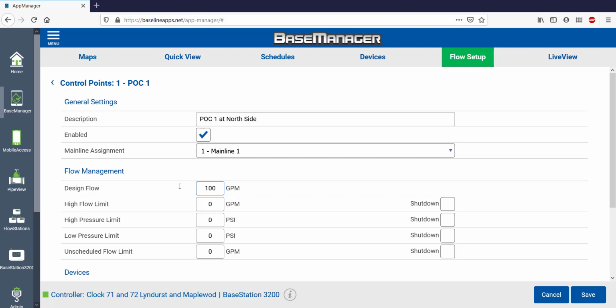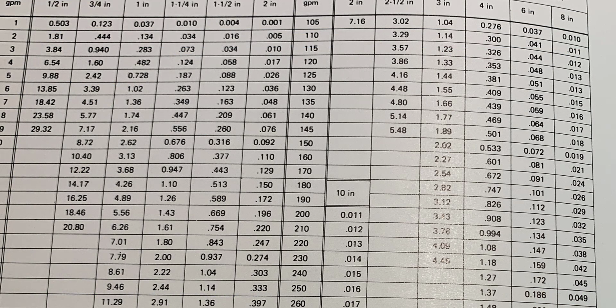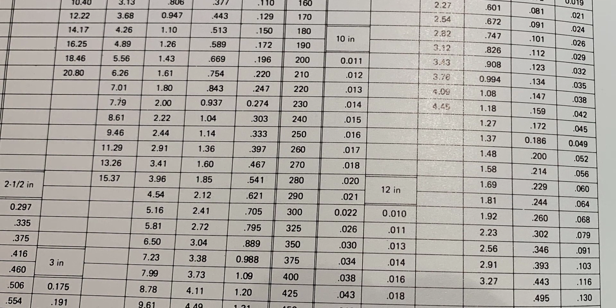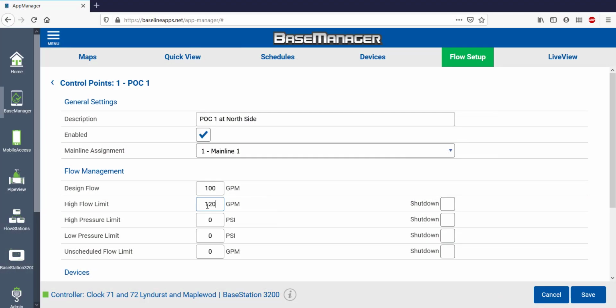I'll set the design flow to 100 GPM, which I based on the size of my control point. I looked up this information in a pipe friction loss chart, but if you're not quite sure how to find this info, your Baseline distributor or Baseline rep can help. I'll try out an additional 20% for the high flow limit, or 120 GPM, and then select Shutdown. The design flow means that I'm okay with 100 GPM all day long, but should it ever exceed 120 GPM, it will alert me and shut down. I don't have any pressure transducers on this project, but if we did, I would set pressure limits here.